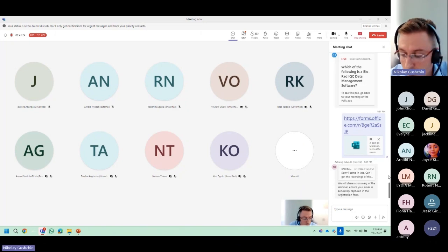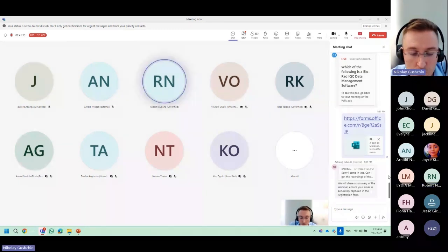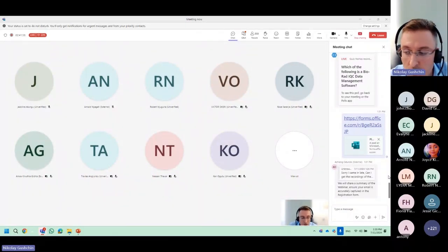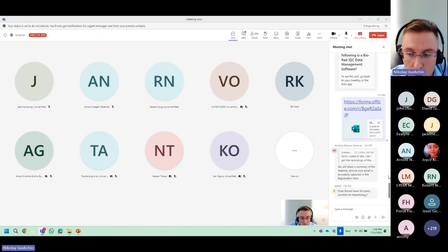What else? Again, there can be a situation when the concentrations, the levels, of the manufacturer controls are not very clinically relevant. That can also create some issues for the lab. You will not have visibility of the clinically important areas of concentration. Well, I would say basically these are the main drawbacks of the instrument manufacturer QC.